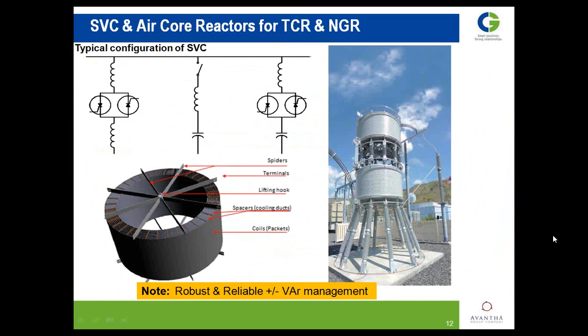It's a fact, whether it is for conventional or non-conventional reactors like air core, its popularity is going up due to its robustness and reliability towards the system. This is one important field for the utilities, and an important instrument to improve the power quality of the system and bring the power factor towards unity, that is, the elimination of the reactive part, which is nothing but more intense towards the active one. Hence I am reducing the IR drop, I am reducing the T and D losses which we normally claim today. So if I improve the power factor, I am reducing the T&D losses. That's the one message for utilities from my side from this slide.